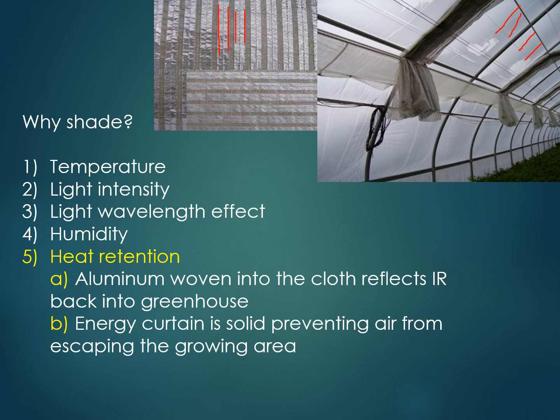And I don't know if you can see in this picture, it might be helpful. The curtain here is actually going down into a pocket, and behind here, it loops over a bar and then hangs over an edge and drops. And that creates a positive seal. So as the curtain moves left to right along this trough, the air can't escape around the curtain and escape into the top. We call this a boot. And you'll see there's some weights in here that hang it over this edge, and it rides on this edge here back and forth to create an airtight gap so that it can slide, but hot air can't escape. So that keeps it nice and buttoned down.